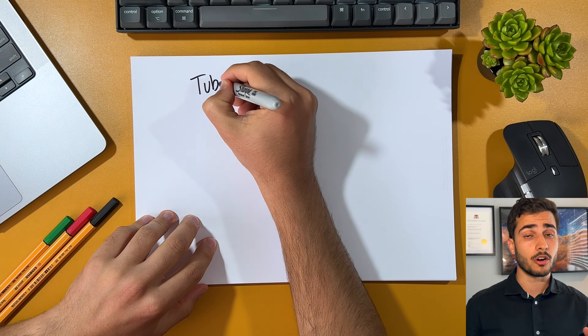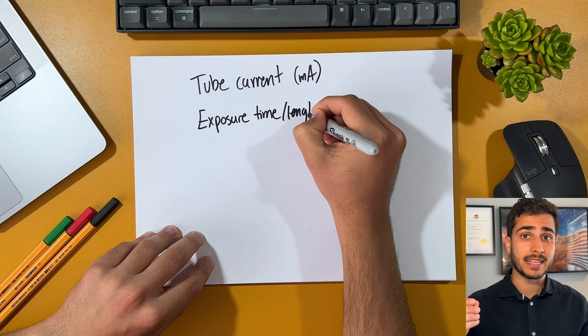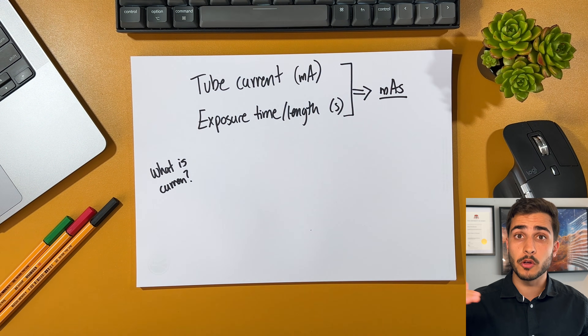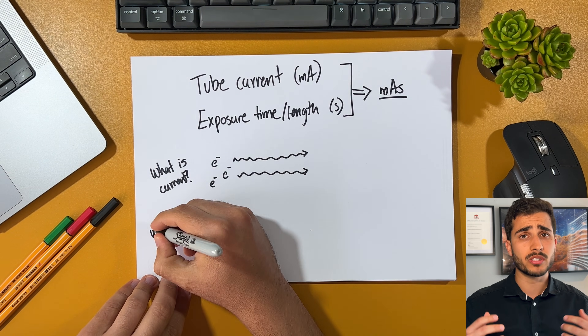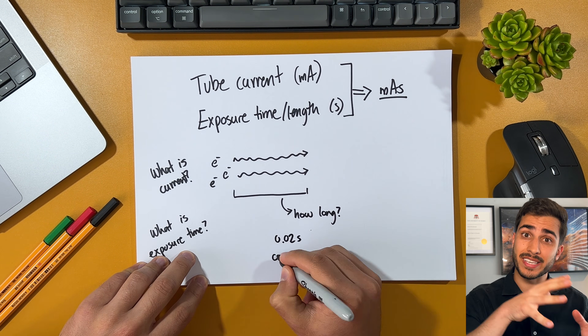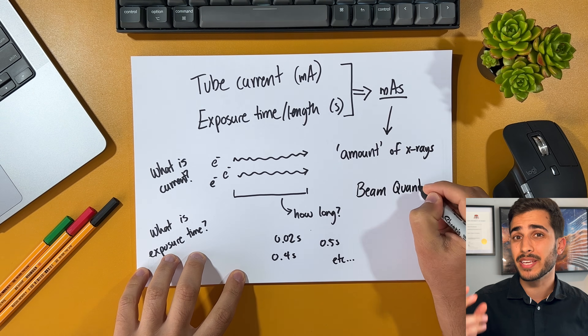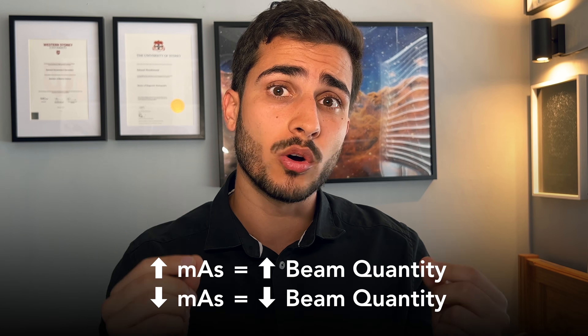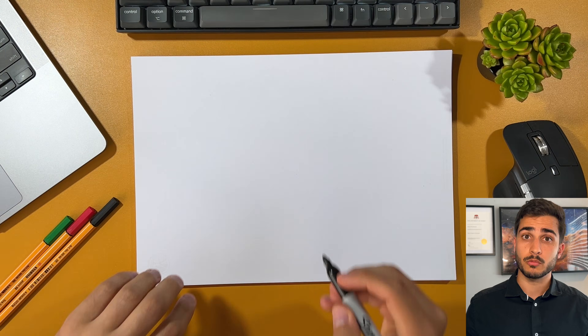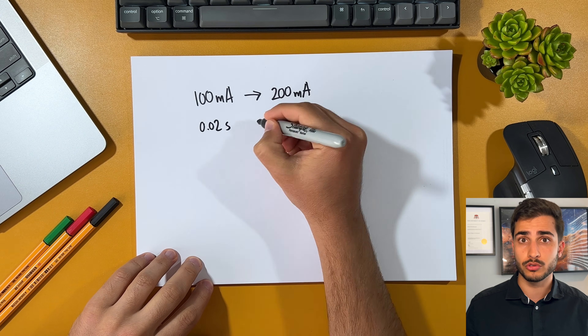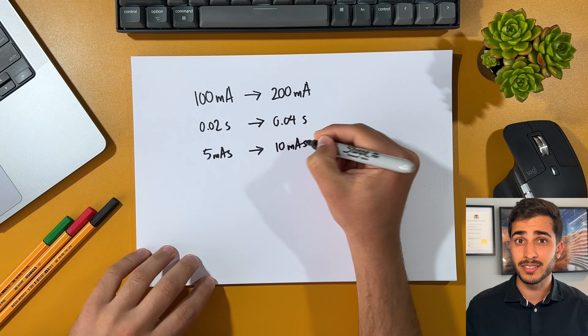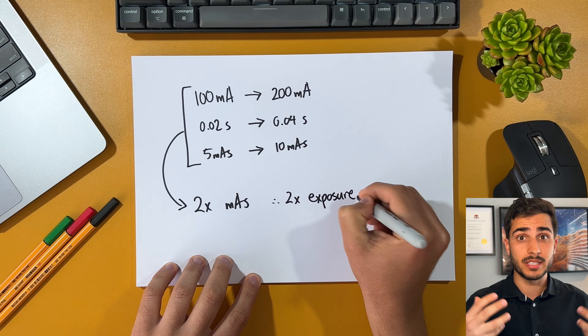Let's start with MAS. MAS is a combination of tube current — MA — and the exposure time or length in seconds. Current is defined as the flow of electrical charge facilitated by electrons, and the length of an exposure is how long we allow these electrons to flow from the cathode to the anode. MAS therefore determines the amount of x-rays coming out of the tube and controls what's known as the beam quantity — the number or quantity of x-ray photons in an exposure event. Whether we increase or decrease the MAS, it increases or decreases the beam quantity linearly. Going from 100 to 200 MA, or 0.02 to 0.04 seconds, or 5 to 10 MAS — all of these scenarios result in doubling the MAS, or basically doubling the exposure or beam quantity.